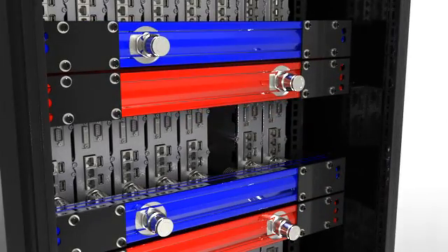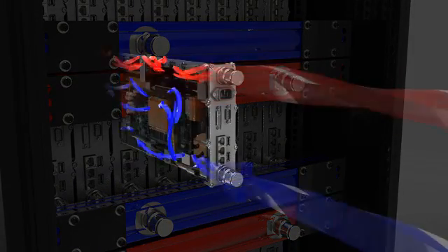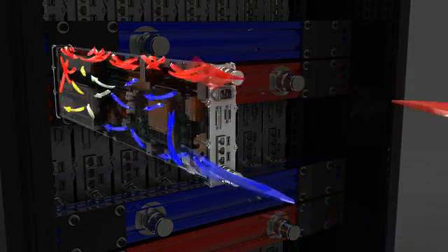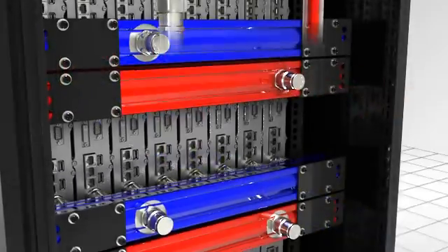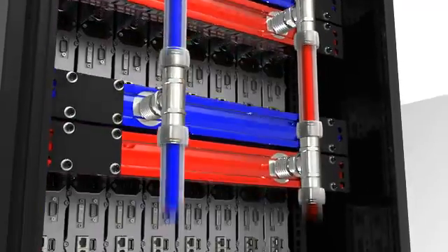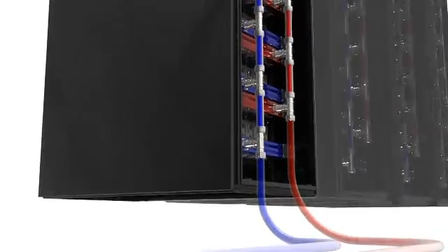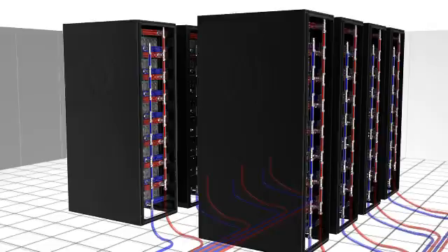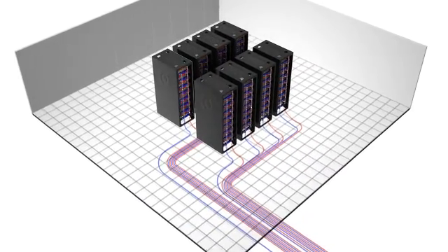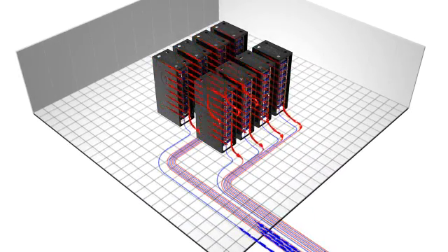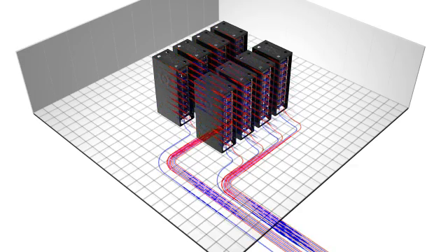Liquid Blade servers mount directly into rack units, connecting to the core coolant exchange system via dripless quick connect fittings. This exchange system pumps core coolant directly into each sealed Liquid Blade server case, fully submerging the blade's internal components in dielectric liquid. The core coolant then flows out of the server chassis to be cooled outside of the data center. This system improves overall performance and efficiency and eliminates the need for additional fans and air conditioning inside the data center. Liquid Blade servers are priced comparably to traditional air-cooled or hybrid-cooled servers, but they last longer, perform better, and reduce total operating costs in the process.